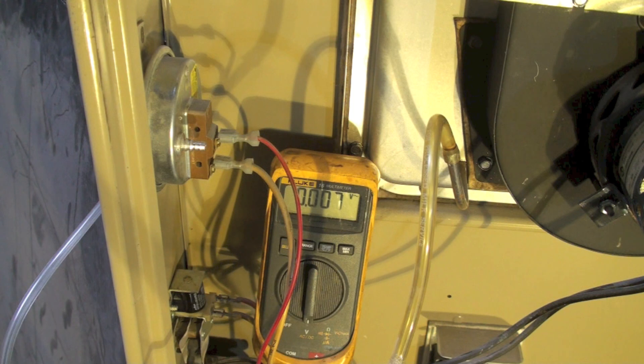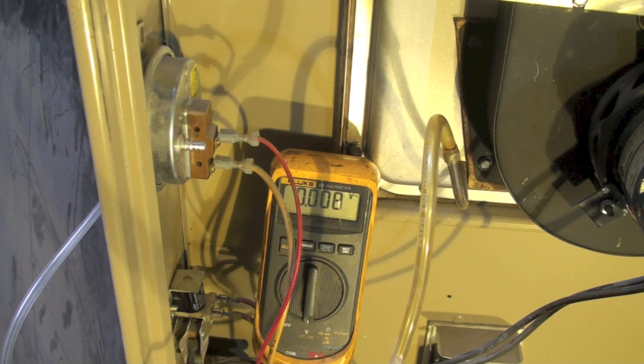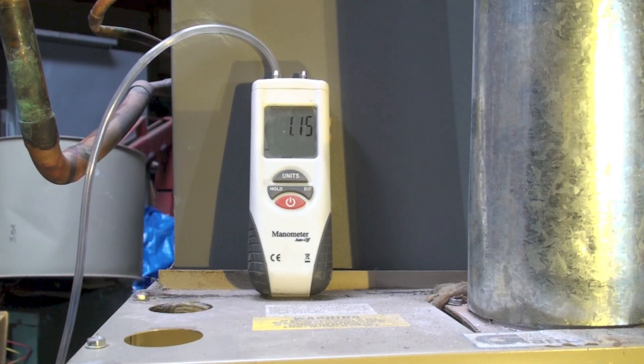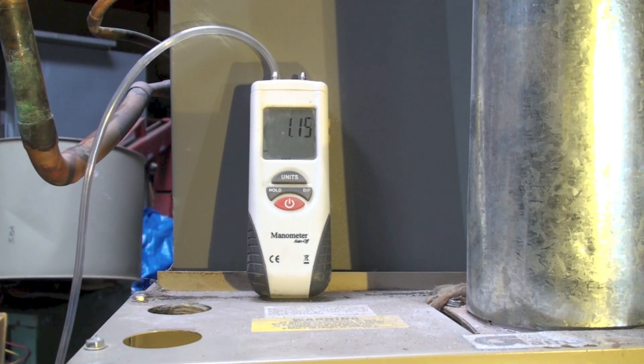Those are pressure switch problems in this thing. And here what I'm showing you are what the vacuum is that the inducer pulls when there's no blockage in the line.